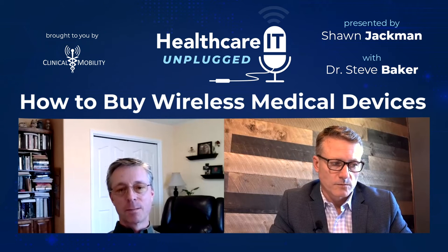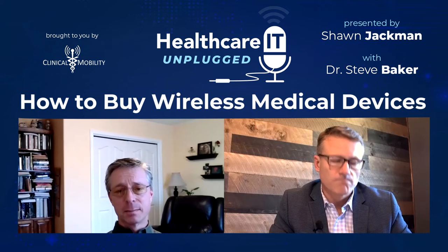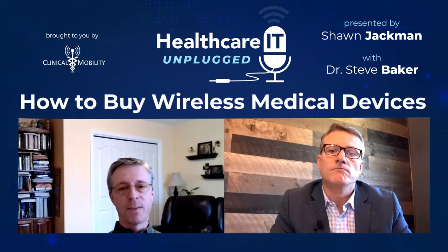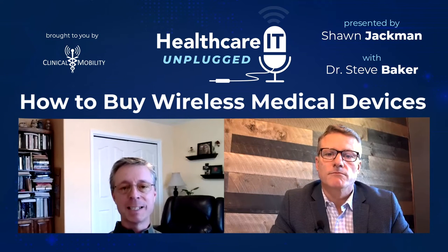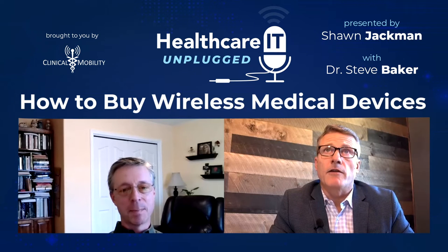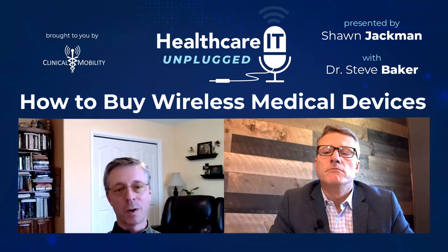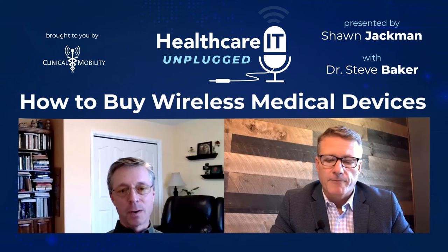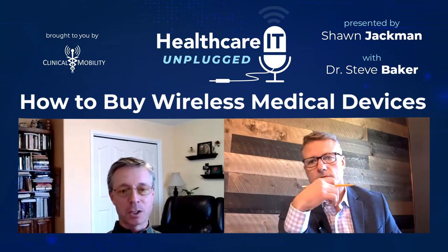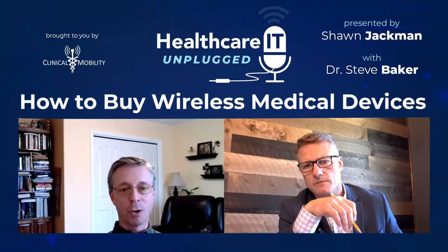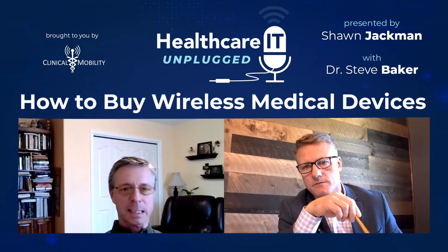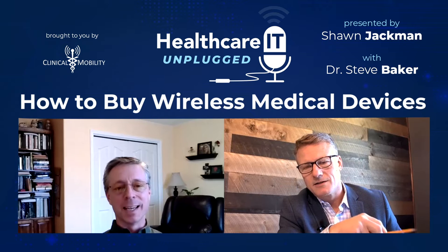Within a medical device, have we changed the intended use? I can put in anybody's Wi-Fi module, and I have not changed the intended use of the medical device - anybody's, in quotes, assuming it's one that actually works. So if my intended use is real-time patient monitoring, and I put in a USB dongle that kind of sometimes works, I'd argue I've changed the intended use because it's now not suitable for real-time monitoring.